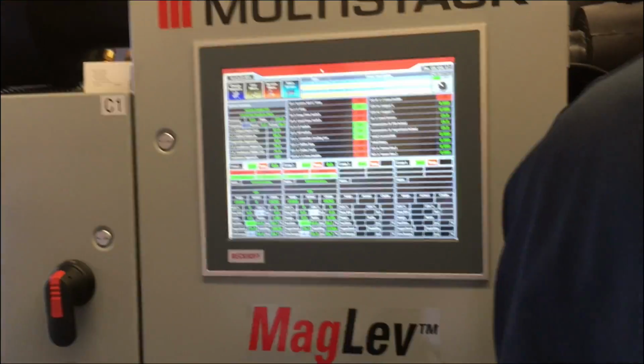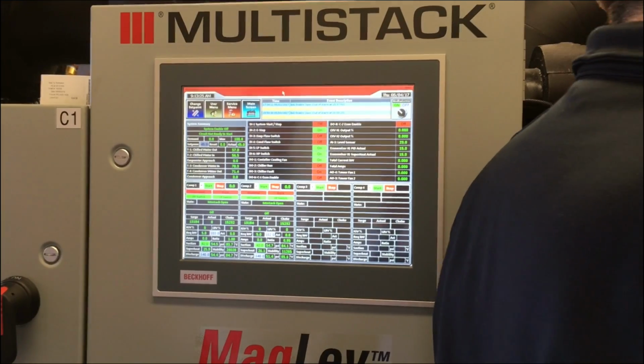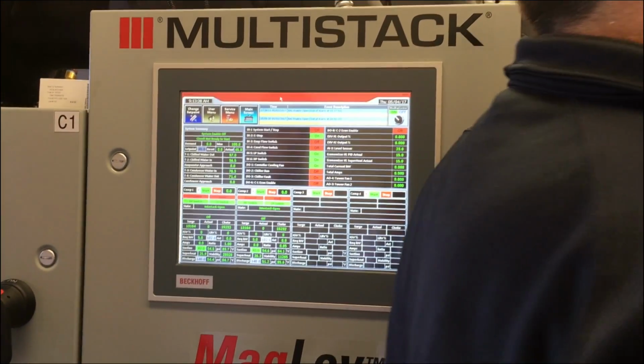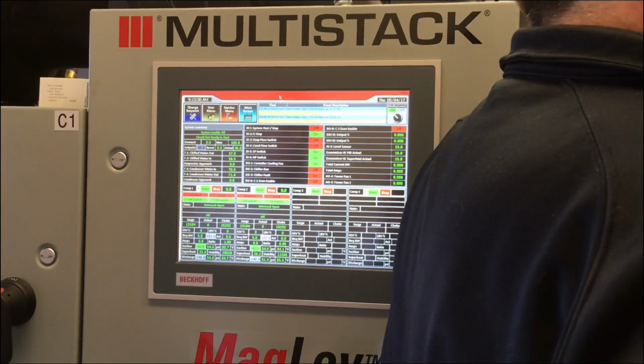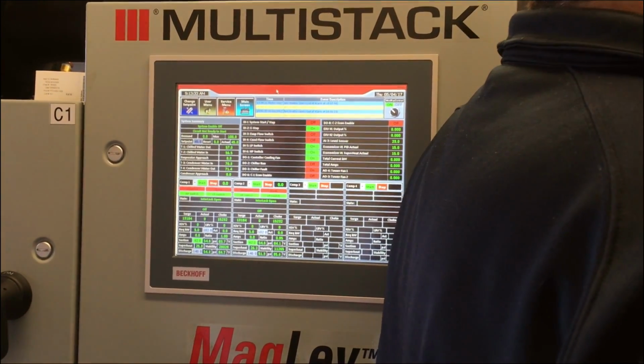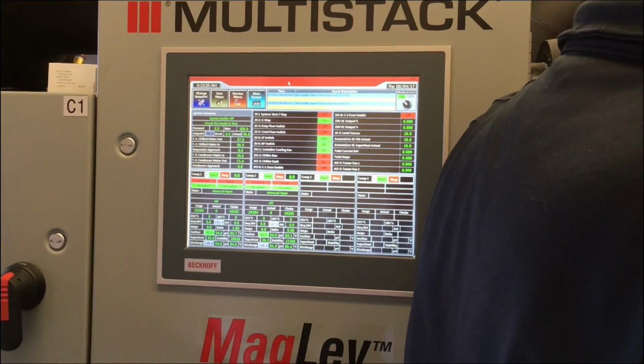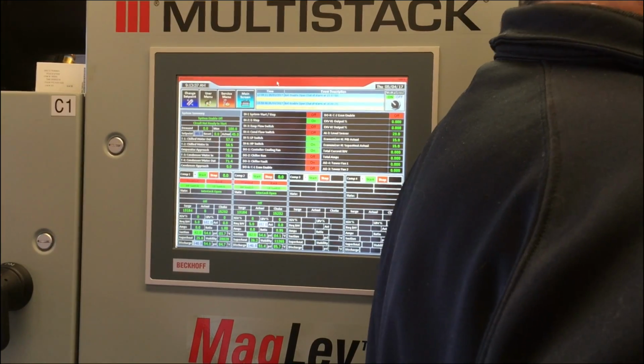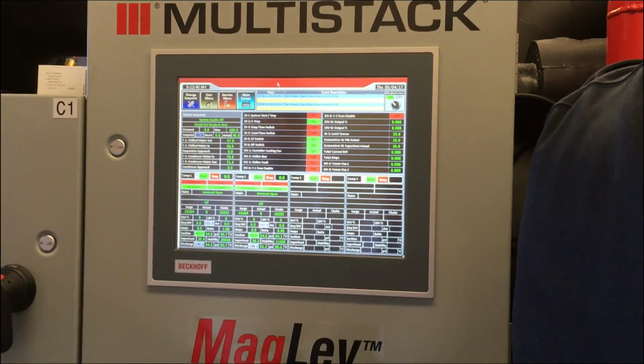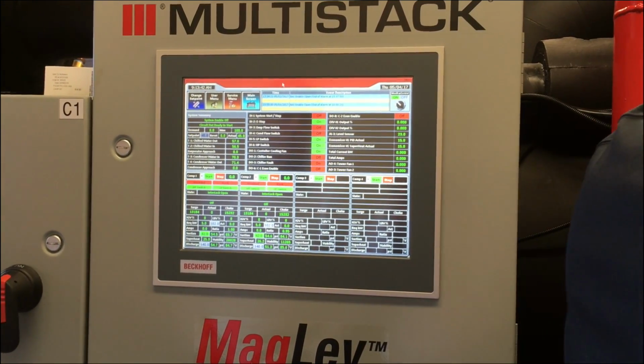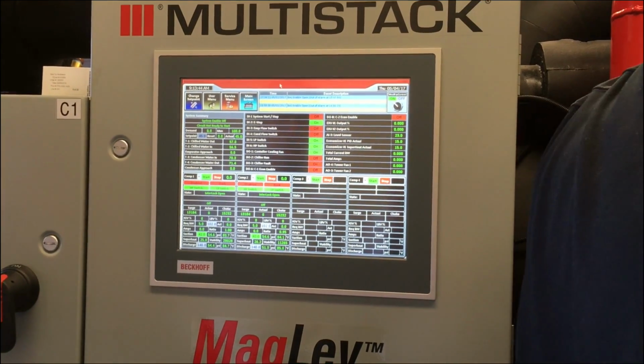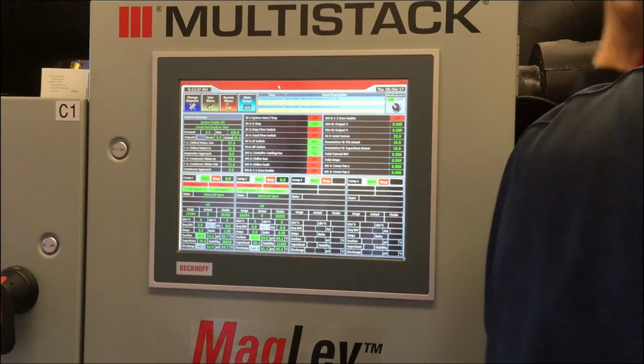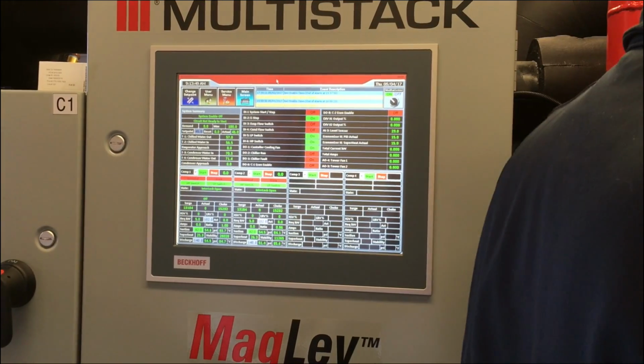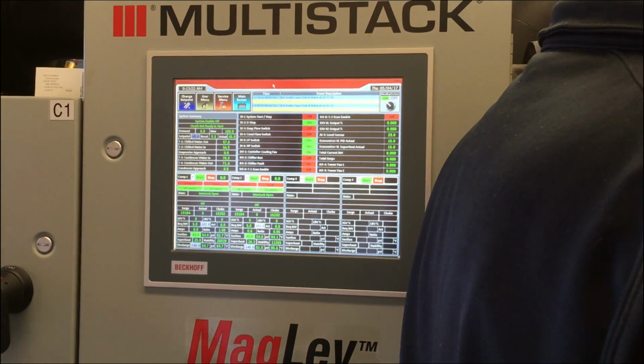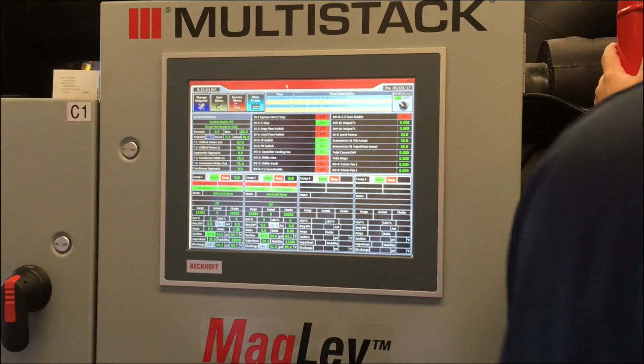If you lose your tower and it gets so high that this refrigerant pressure becomes so high that this can't push on, because this is just a pump. If you think about that chiller as a pump and not a piston, it'll make sense, because just like any other pump, if it can't push the column, it's going to start cavitating and skipping and spinning. So if that happens, this check valve will bang, because it's trying to push this way, it's fighting, getting pushed back, fighting, and you'll hear this bang. A lot of times I'll ask them, what's your cooling tower temp? And they'll say it's 117 degrees. I say, well, maybe we have a cooling tower issue, and we'll go there.